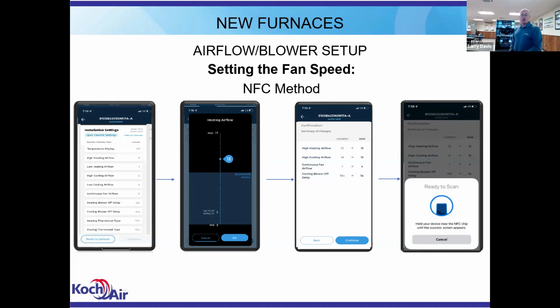You're going to set the temperature display. You can turn the temperature display on and off on the mid-tier furnace. You can set your high heat airflow. You can set your low heat airflow, or you can let the board do that automatically. You'll set your high cooling airflow. When you go into that menu, we should see that here in another slide. It'll allow you to tell it what size air conditioner you have, what tonnage, and then it'll give you the recommended range for that tonnage. Okay. It's only going to let you select the size of air conditioner that is approved for that size furnace. In other words, it won't let you put a 5-ton air conditioner on a furnace with a 3-ton drive. Okay. Those safeguards are programmed in.